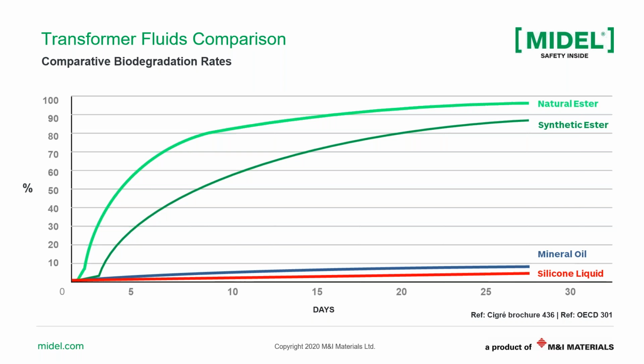And here you see 3 or 4 liquids: natural ester, synthetic ester, mineral oil, and silicone liquid. You can see mineral oil and silicone liquid will not biodegrade within this test to more than 10%, so very low, so they will be sustained in the environment if you have spillage. On the other hand, natural esters and synthetic esters can reach biodegradation of more than 85%. And so this allows, as I said, reduced funding and reduced procedures for cleanup if needed, if spillage occurs.